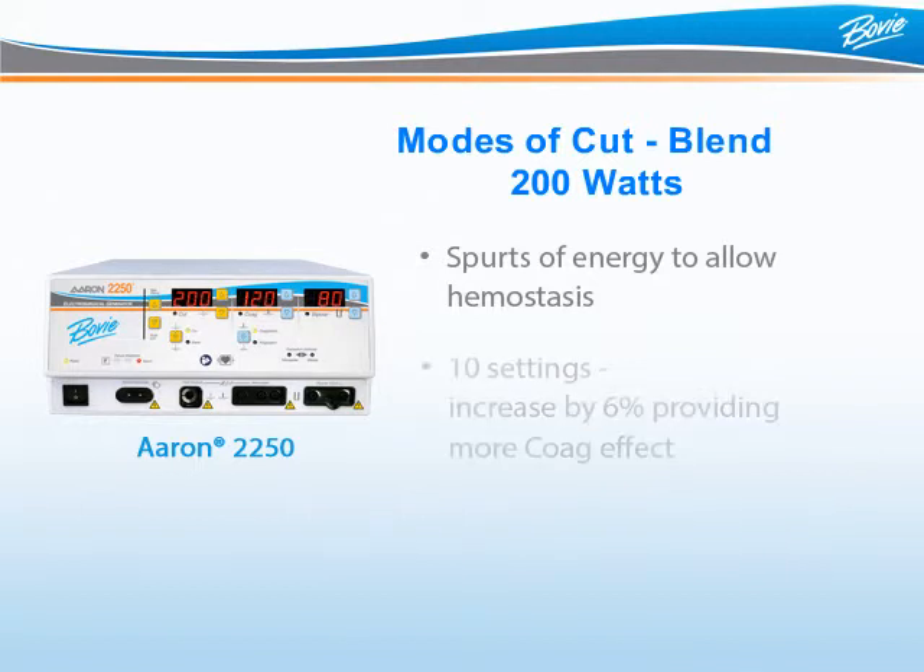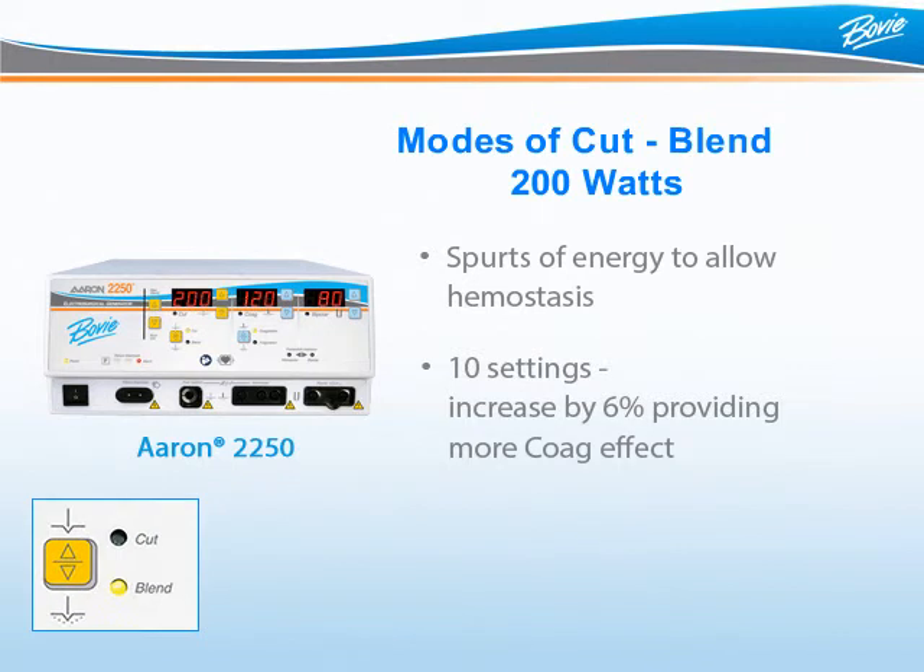Blend is a mode of cut that delivers energy in spurts. In between the spurts of energy is a cooling period that allows for hemostasis. The Aaron 2250 offers 10 blend settings; each level of blend is increased by 6%. The higher the blend setting, the longer the cooling period and the more hemostasis. To activate blend mode, press the double triangle button until the blend LED is lit. To adjust the hemostasis, use the up-down button next to the vertical LED bar.